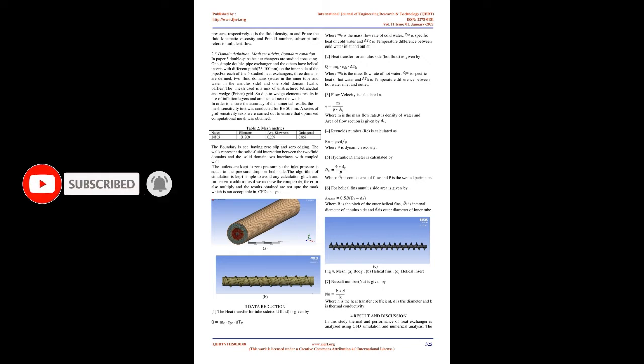The diameter is calculated by considering the turbulent flow condition, which will help in increasing the chances of heat transfer rates. The CFD software Fluent and Design Modeler were adopted to establish the models and analyze the flow and heat transfer properties. Water is used as it is an incompressible fluid with constant properties. Furthermore, the fluid flow and heat transfer processes are considered in the turbulent regime and steady state. Within the calculation range, all Re are greater than 5000 for the inner pipe and greater than 3000 for the annulus region. The leak between the helical wall and the annulus pipe is very small and can be neglected.